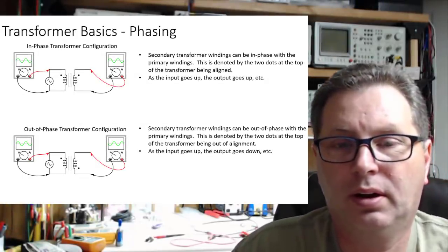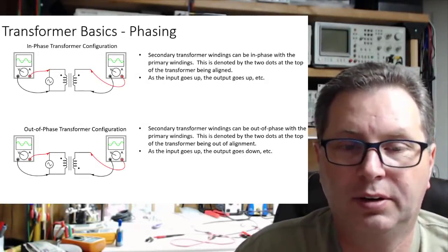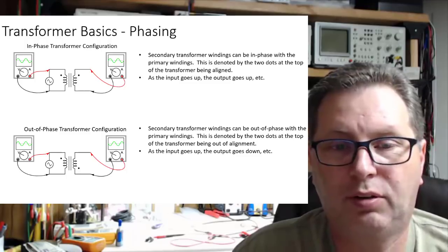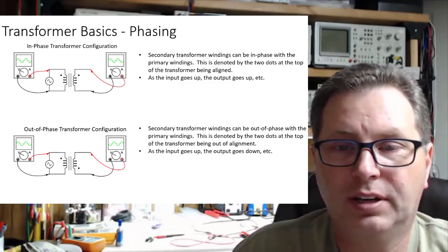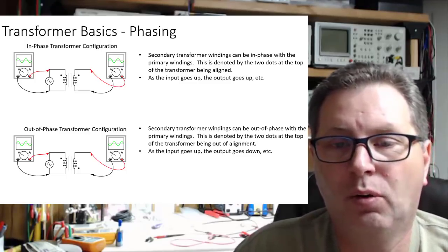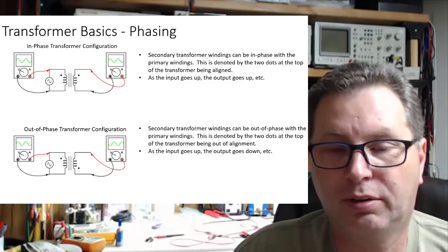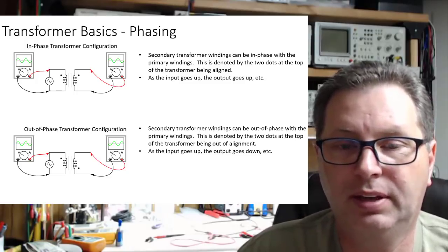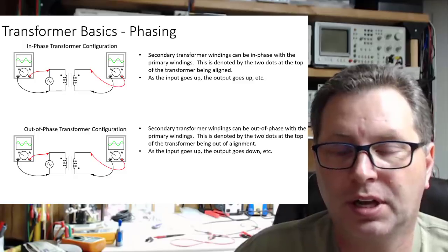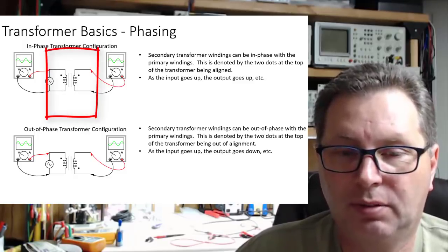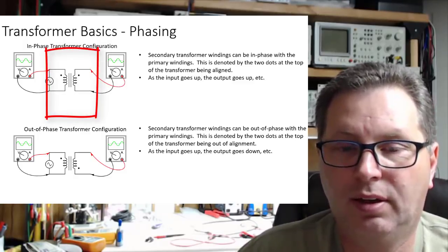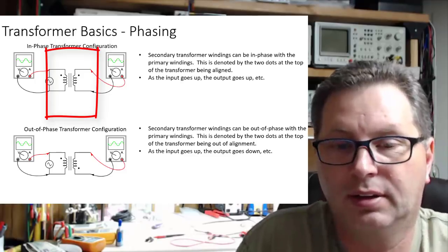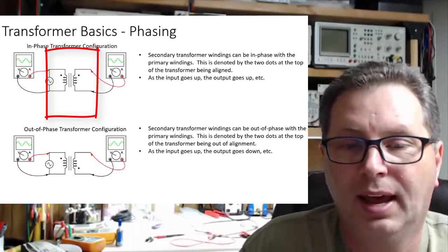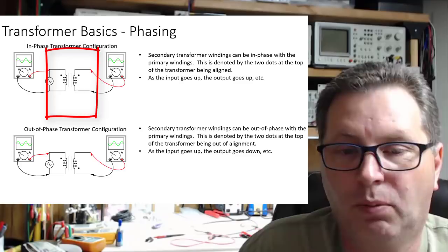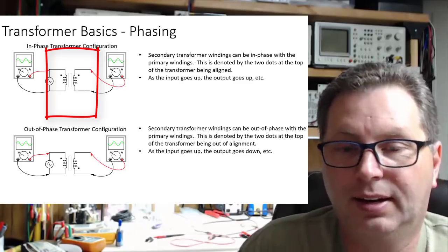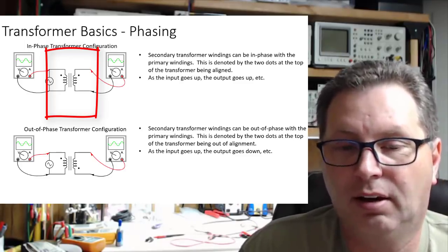Just two more quick concepts before we dive into one of these bucking transformers. First is phasing. On this transformer symbol between the two voltmeters, you've got windings on the primary and secondary, vertical lines representing the core, and two little dots above it. Those dots denote the phasing of the transformer.